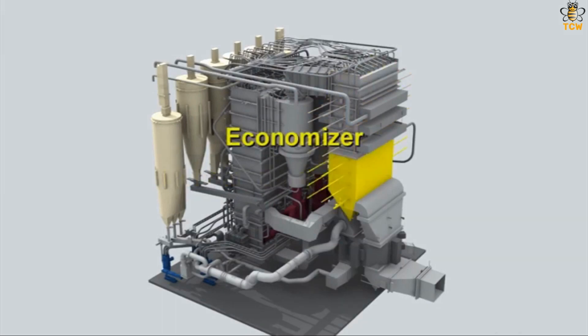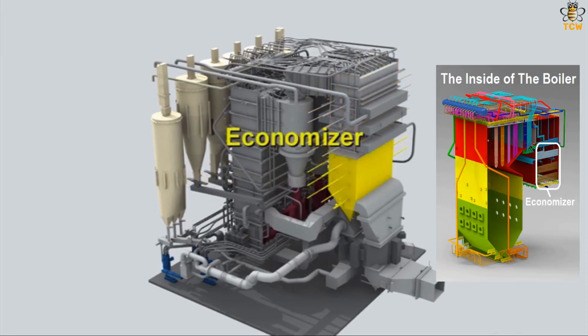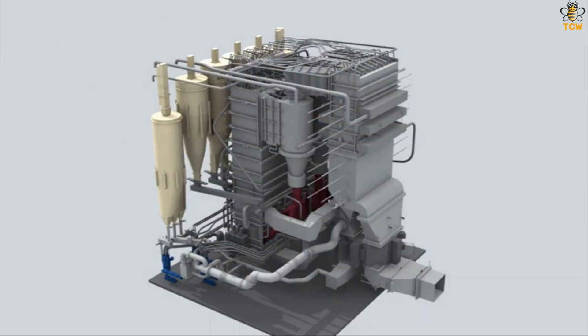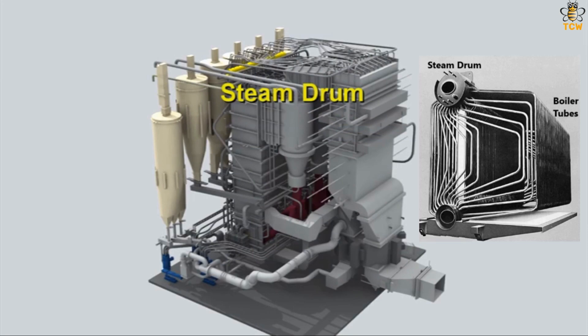Next is the economizer. The economizer is an arrangement of pipes at the end of the hot gas flow in the boiler that serves to heat the feed water entering the boiler. The steam drum is a temporary steam storage container in boilers. The steam drum serves to separate the phase of water carried by steam.